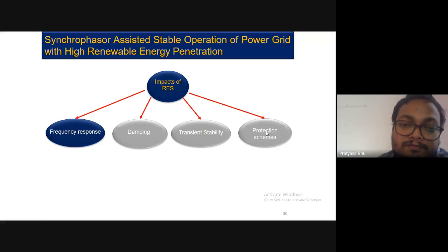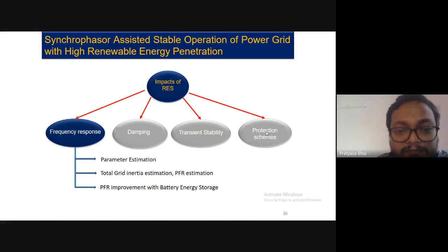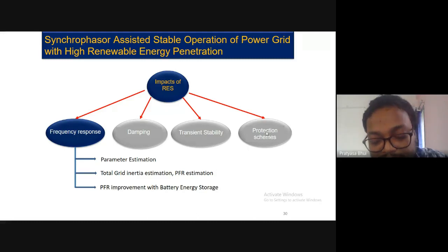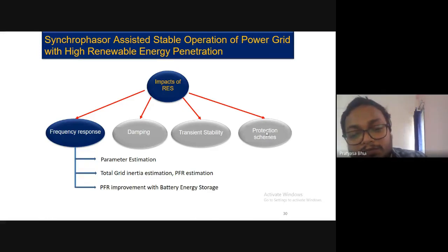So for frequency response, we can estimate parameters like generator inertia or the total inertia in the grid, and then primary frequency response estimation. Basically, whenever there is any frequency disturbance, how much power is increased to improve the frequency. Those things can be estimated from measurements. And then you can use some battery energy storage or renewables or even electric vehicles. You can control the power from this power electronic interface storage or renewables to improve the frequency response.